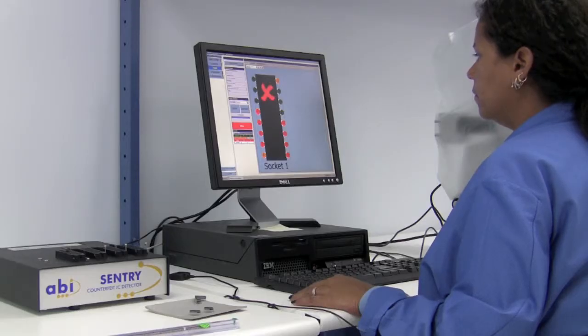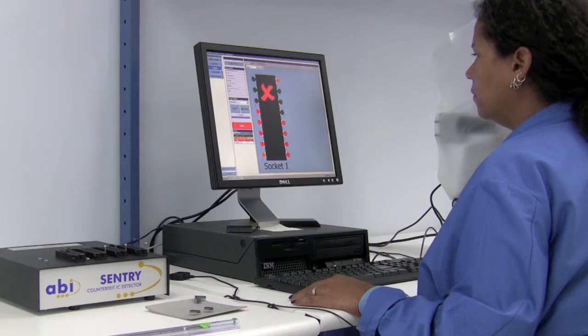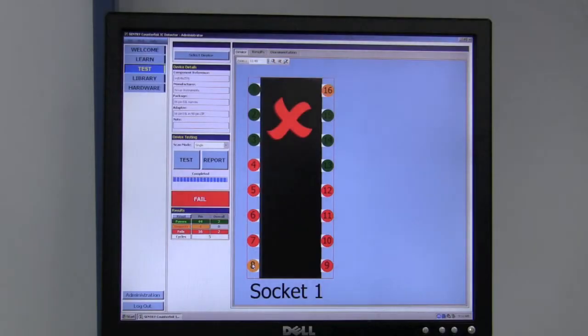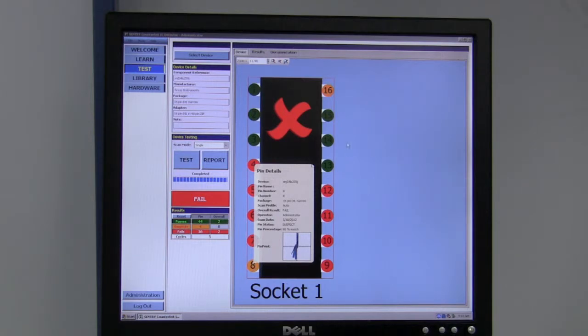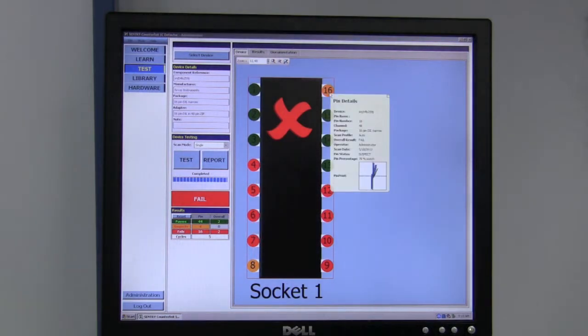At this point, we can click on each individual pin and see what the results were, get a readout of the graph, and the percentage of variance from that pin to the learned device's pin.